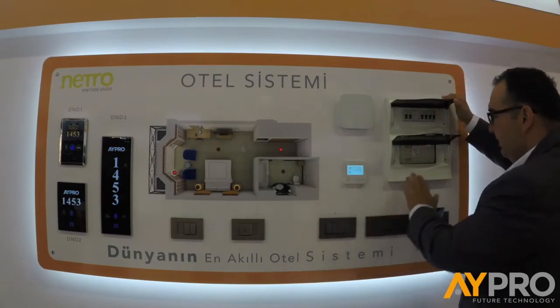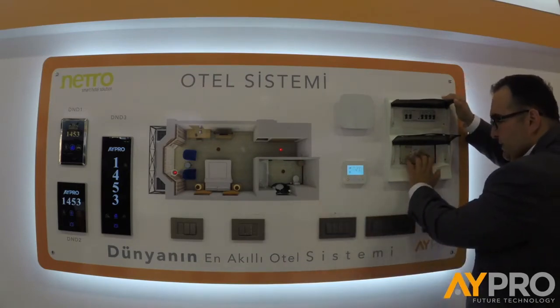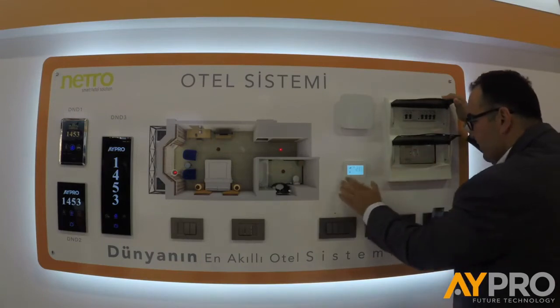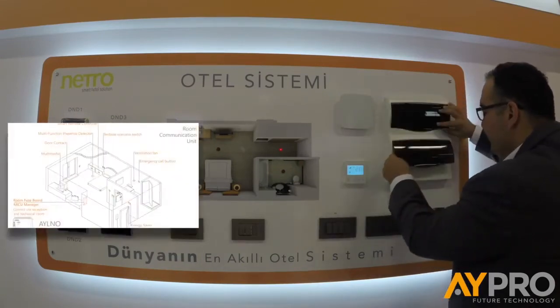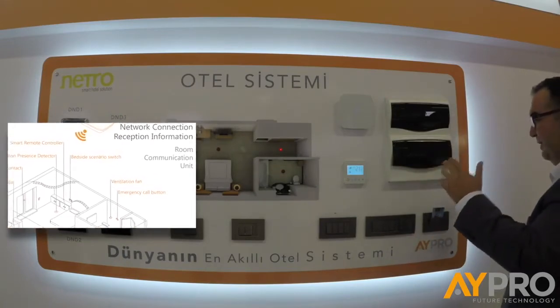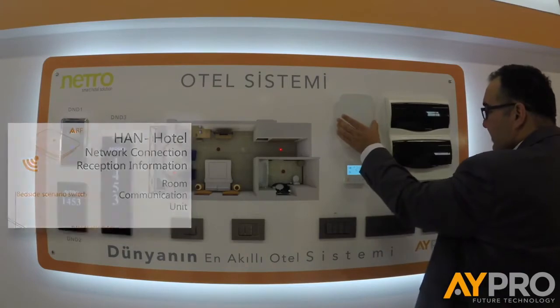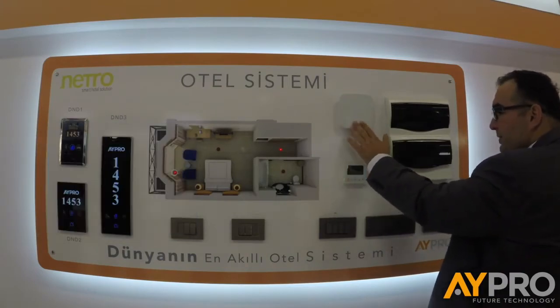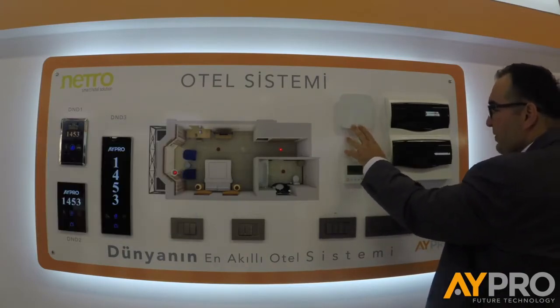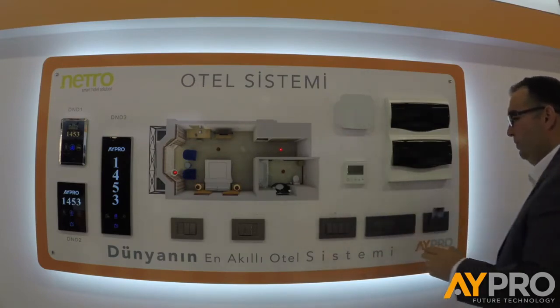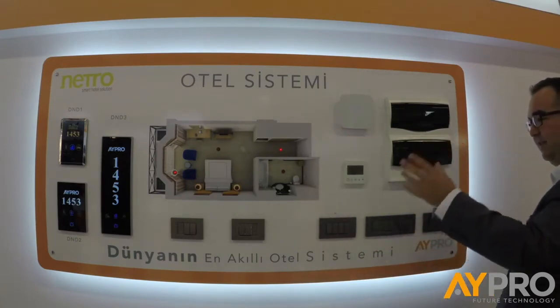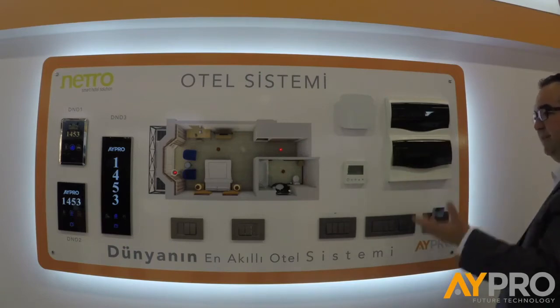So in one room, we have one room controller on the panel, and you have one thermostat here. And the communication is very easy, because we don't need any Cat5 cables or any bus cables through the hotel room. We just have the gateway here, and the gateway stays in the corridor, and this gateway can talk with 10 up to 15 different rooms. So you can use the existing hotel system to integrate with the smart system.